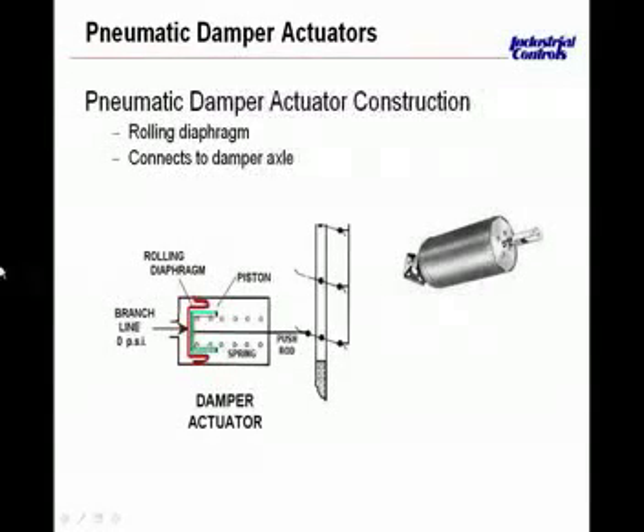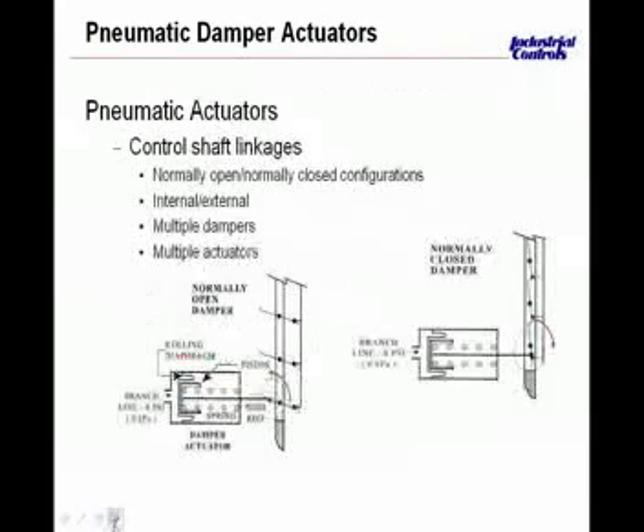Take a look at some more damper actuators here. Right, and to Carl's point, you can see the right-hand side is noted as normally closed, and there the actuator stem is connected to the bottom side of the axle. So as the branch line pressure increases, the stem is going to extend, driving the damper open.